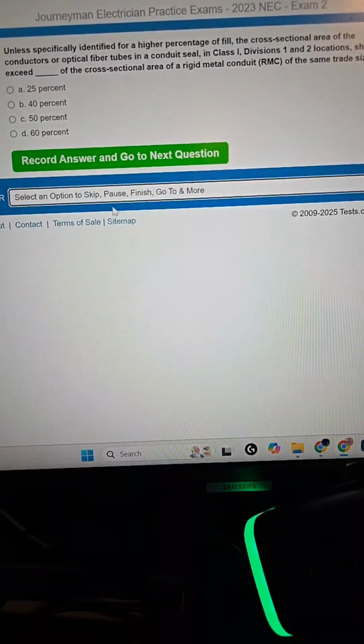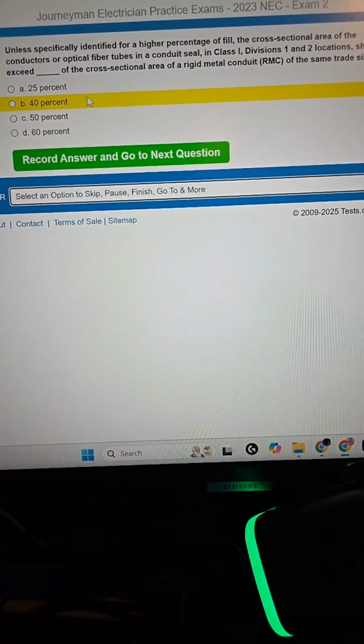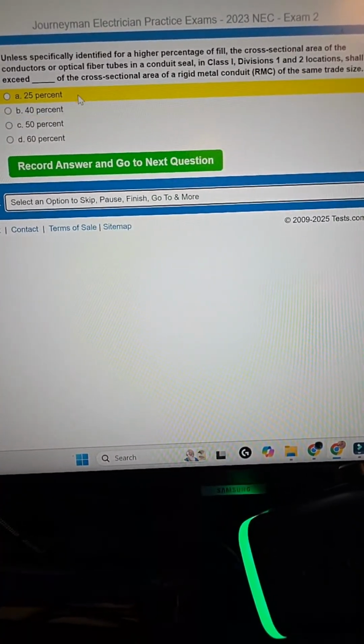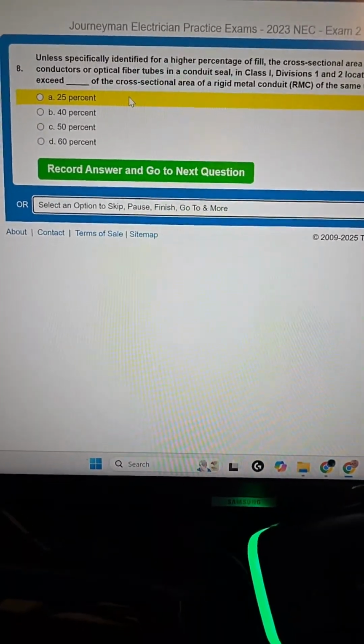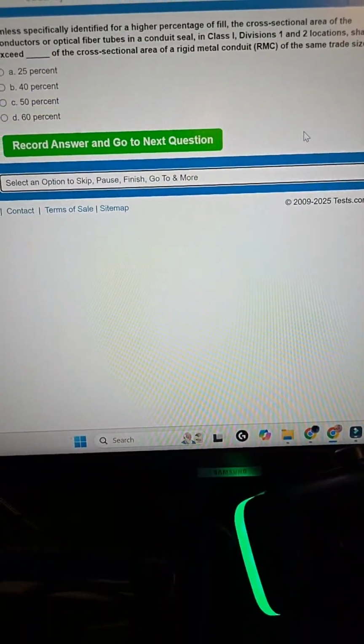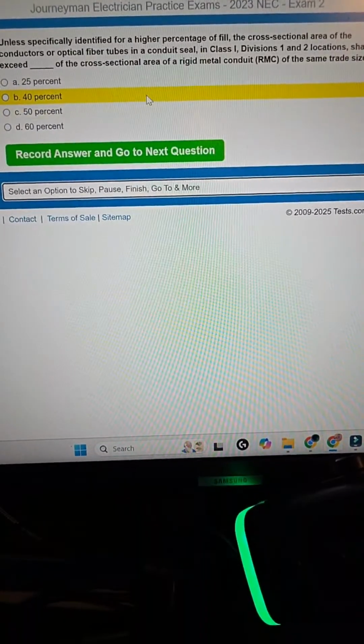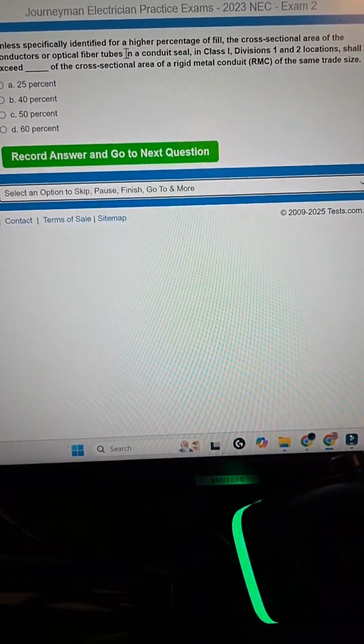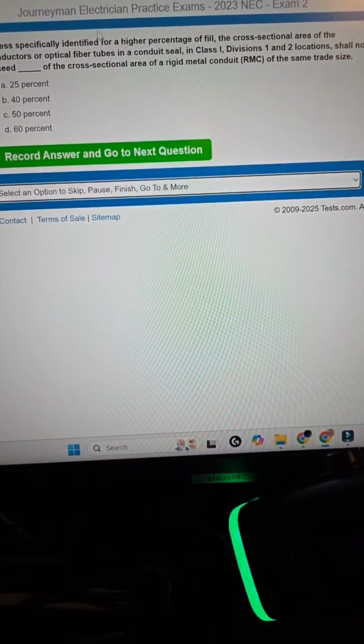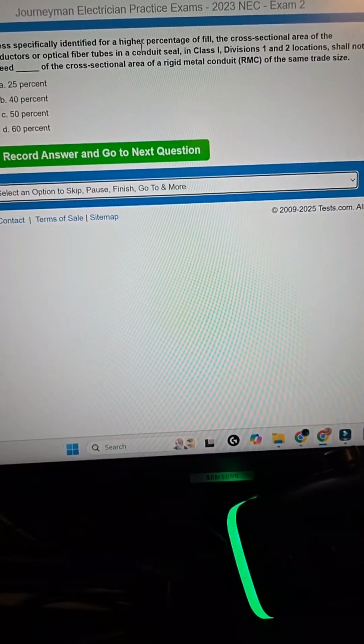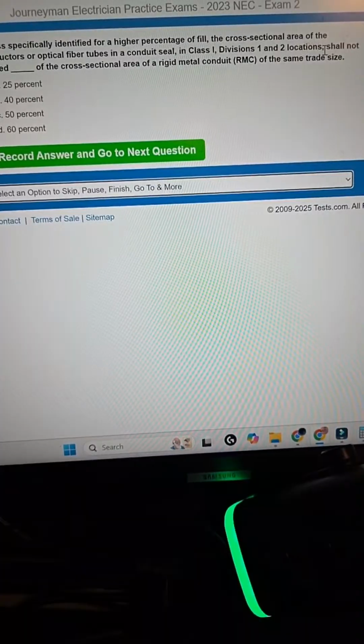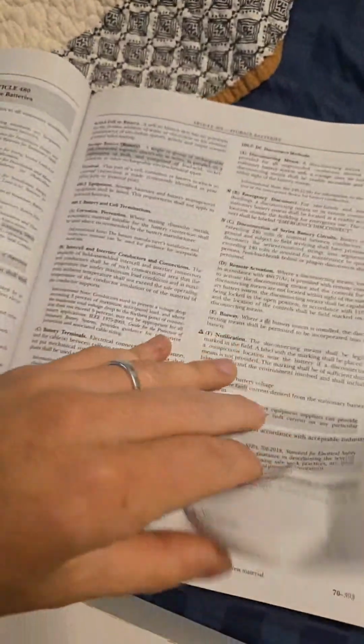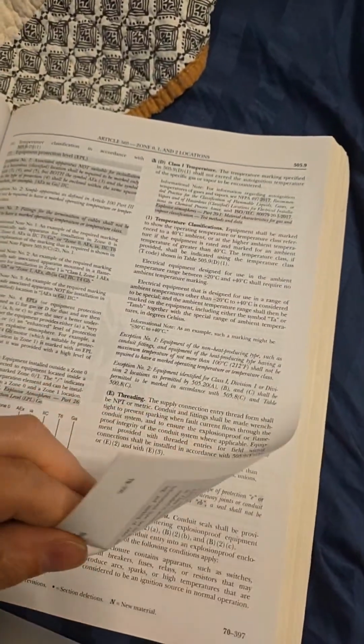We could skip. I'm not going to skip it. We could find that. We could help you guys out. Well, let's just look it up. We're gonna lose time, but let's just look it up. Unless specifically identified for a higher percentage of fill, the cross-sectional area of conductors and optical fiber tubes in a conduit seal in a Class 1, Division 1 and Division 2. So we got a Class 1, Division 1 and 2. So let's go here. What's up, Russ? Let's go here to Class 1, Division 1.